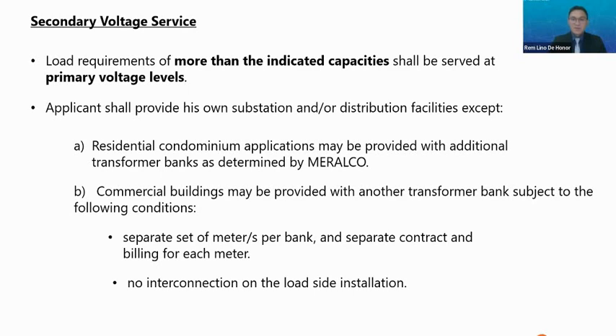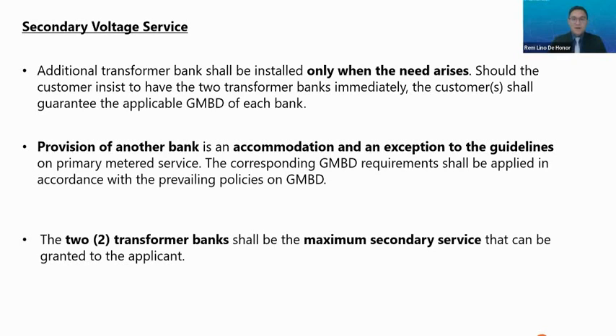Commercial buildings may be provided with another transformer bank subject to the following conditions. First, separate sets of meters per bank and a separate contract and billing for each meter. No interconnection on the load side installation. An additional transformer bank shall be installed only when the need arises, based on the recommendation of Meralco. Provision of another bank is an accommodation and an exemption to the guidelines. Lastly, two transformer banks shall be the maximum for secondary service.